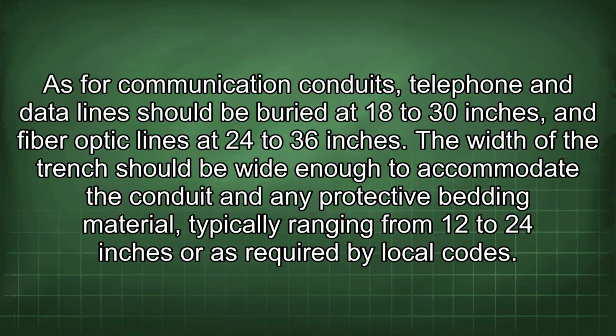As for communication conduits, telephone and data lines should be buried at 18 to 30 inches, and fiber optic lines at 24 to 36 inches. The width of the trench should be wide enough to accommodate the conduit and any protective bedding material, typically ranging from 12 to 24 inches or as required by local codes.